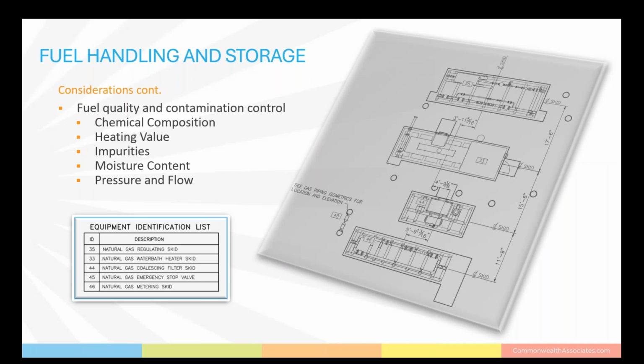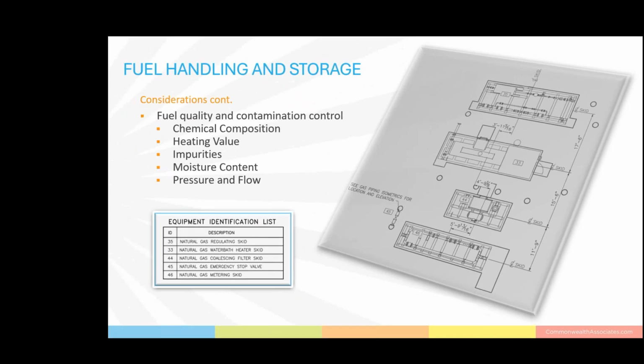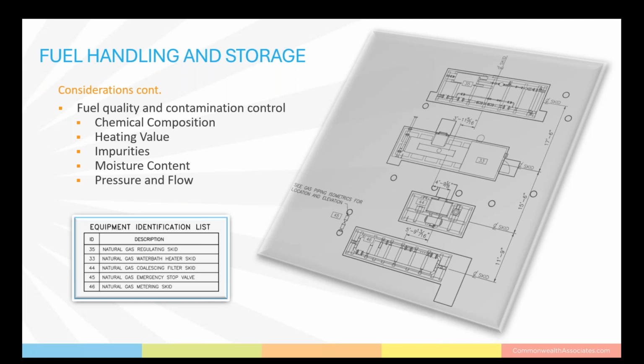Factors that can drive the arrangement for natural gas include whether or not it's already on site. If not already available, it will most likely require a metering station that typically belongs to the gas supplier. When using natural gas, there are other factors to consider for required equipment. The gas yard layout shown in this example highlights 4 of the skids that may be required based on fuel quality. The chemical composition of natural gas can vary depending on the source and geological formation. Natural gas primarily consists of methane, but it may also contain various amounts of other hydrocarbons. The relative proportions of these components can affect the quality and energy content of the gas, known as its heating value. The higher the heating value, the more energy rich the fuel is.